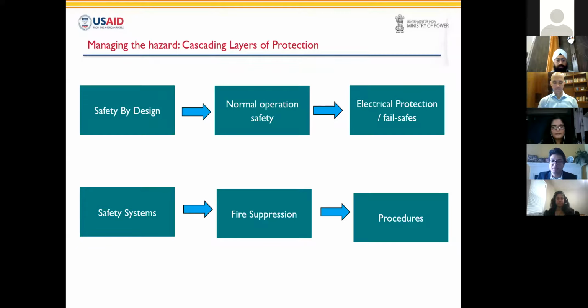For my Hindi-speaking colleagues, safety measures are required to be like Mahabharat's Chakravyu. At the outermost layer, you have monitoring for off-gases, abnormal thermal or electric conditions. At the next layer, you have preventative measures like venting, HVAC, mechanical disconnects, and electrical disconnects. At the innermost layer, you have suppression and containment strategies. Like we are following social distancing these days, the system subcomponents are required to have clearances and safeguards, such that thermal runaway in one cell or rack or module is not propagated to the others. This requirement is actually ingrained in UL 9540. The testing requirements for that are in 9540A. In the worst case scenario, if the Chakravyu is breached, training and procedures should be in place for emergency responders.